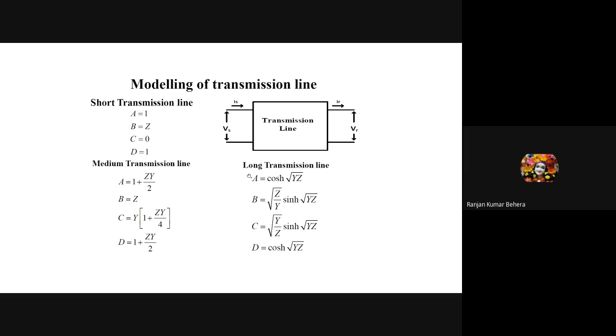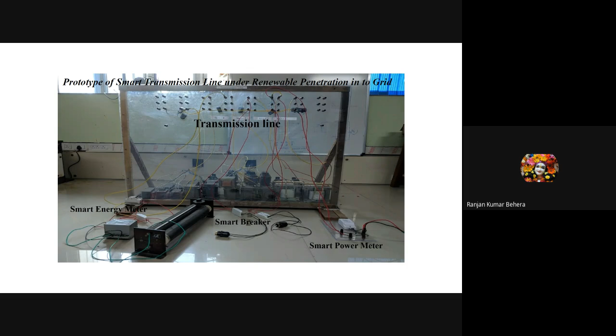How do you test it? You test it using the Ferranti effect. When you apply voltage, the Ferranti effect means your load end voltage will be higher compared to the sending end voltage. That is what we have studied here.